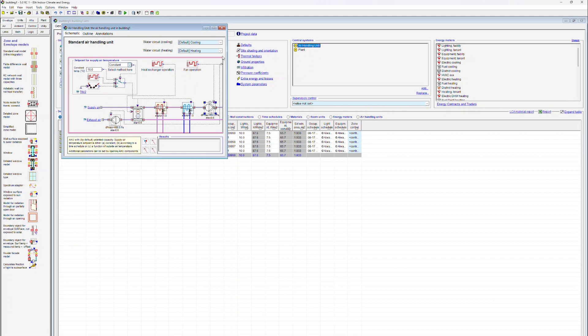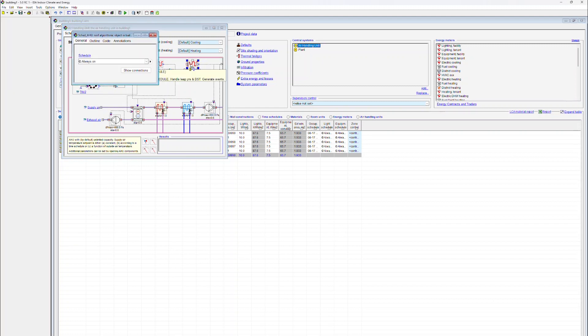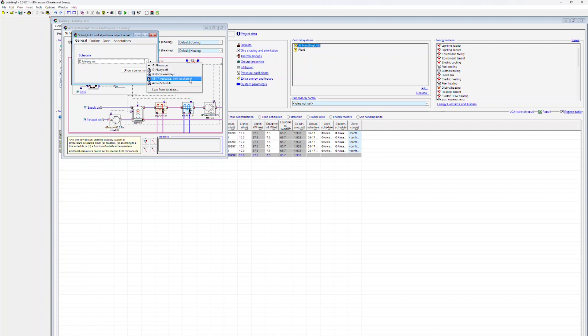There are different ways how the air supply to a zone can be controlled. The fans can either meet the fresh air requirements of the zone, the fresh air requirements can be multiplied, or completely turned off. We are now going to associate a certain schedule with the operation of the fans.